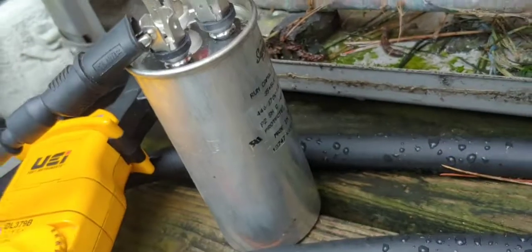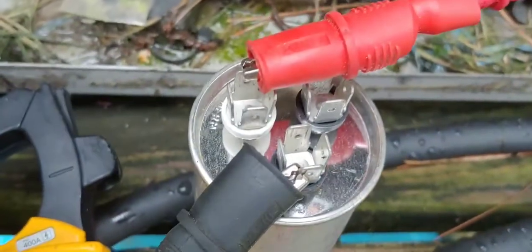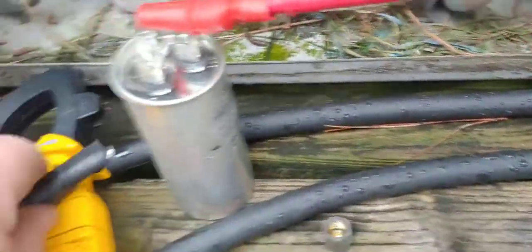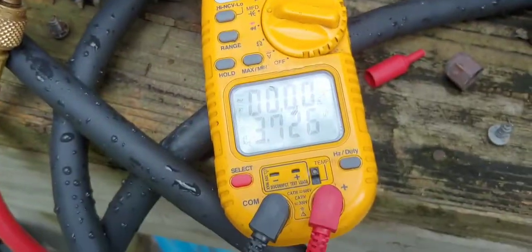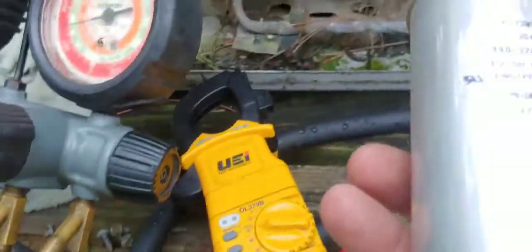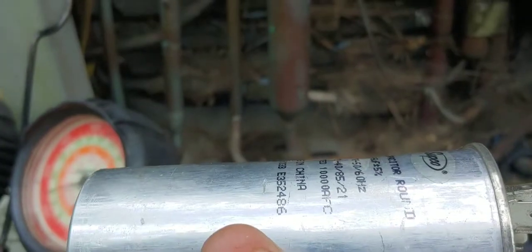Someone had squeezed the bejesus out of this capacitor. This is a Supco brand, 35 plus 5. We're on our common and our hermetic — we're getting 9.4. That is weak. That could cause the breaker to trip. So we're going to replace this. We can check the fan too — 3.7, so it's weak. This thing's weak. They had squeezed the crap out of it — you can see where they squeezed it. No squeezing it.